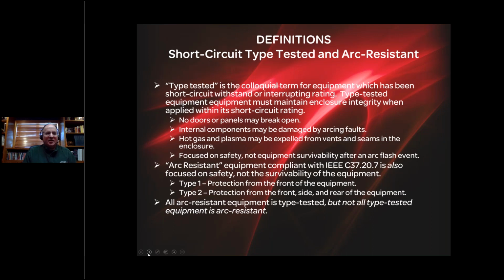And the purpose, as we'll see in mechanical venting, is to vent that out of plenums out the top of the gear and safely expel it so it isn't expelled out the front of the gear and it hurts people and causes injuries. So hot gas and plasma in standard equipment may be expelled from vents and seams in the enclosure, and it still passes type testing. But again, no doors or panels may break open. In other words, the enclosure may not rupture. If the enclosure ruptures, it fails type testing and would have to be redesigned by the manufacturer.